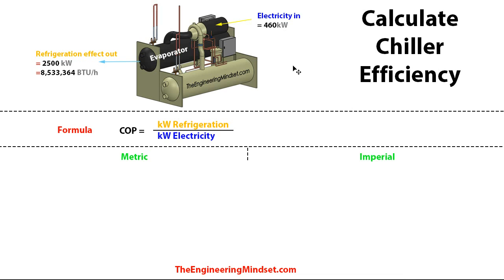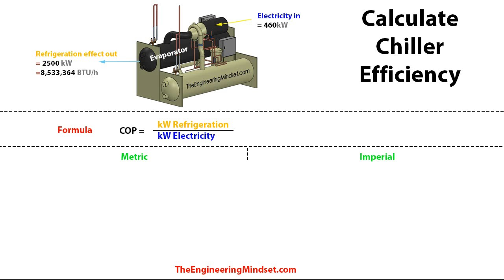The first part of the formula that we need is the electricity in, and that's measured in kilowatts. Now that's very easy to get hold of — you just put on a meter, maybe from your BMS or on the head end of the control panel. Otherwise you can put on some temporary metering and actually grab these numbers. The power consumption by this unit will vary by the amount of load that's placed on the compressor, so as the cooling load of the chiller changes, so will the load on the compressor. So you want to keep a log of that.